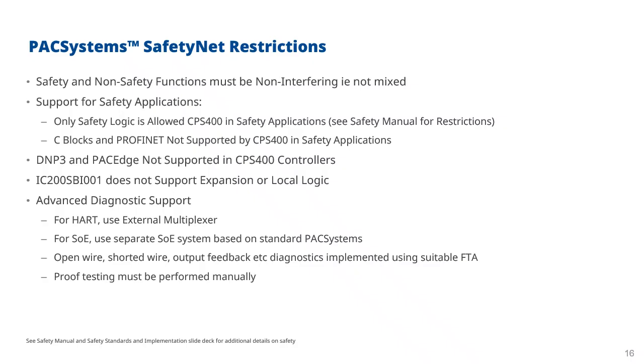And the SBI, that's the safety bus interface, does not support any expansion I/O, and it doesn't support any local logic. It's dedicated for being used as a safety bus interface only. Now, there are potentially some advanced diagnostics that you might want to implement in your project. So for HART, if you want HART, you'd have to use an external SIL approved multiplexer, and that would bring out the HART signals to an external system.